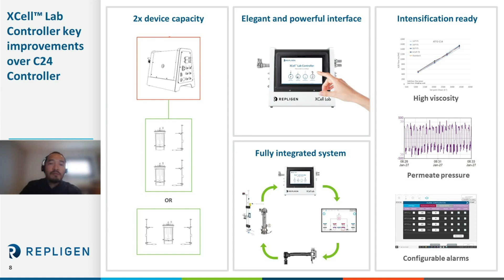And finally, to the right, I wanted to talk a little bit more about this additional new functionality that's unavailable with the current C24. This flow-based control actually allows higher precision across a variety of cell culture conditions, particularly more challenging viscosities. I'm going to talk more about this later, but that's a very important point. Second, here you can see the option of permeate pressure measurement, basically to enable real-time monitoring of filter performance over the course of the run. And you can configure alarms based on permeate pressure, for example, an alarm indicating filter fouling. So these are great improvements to this new controller.